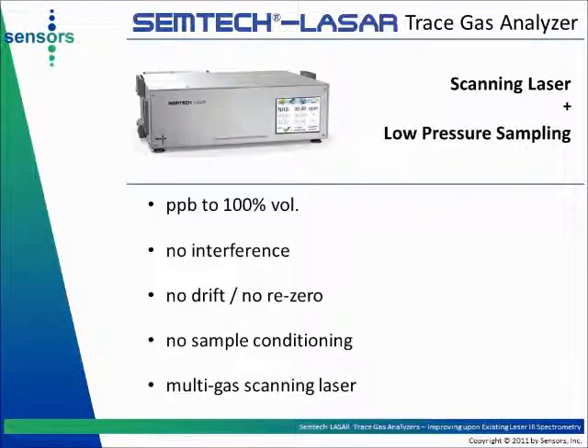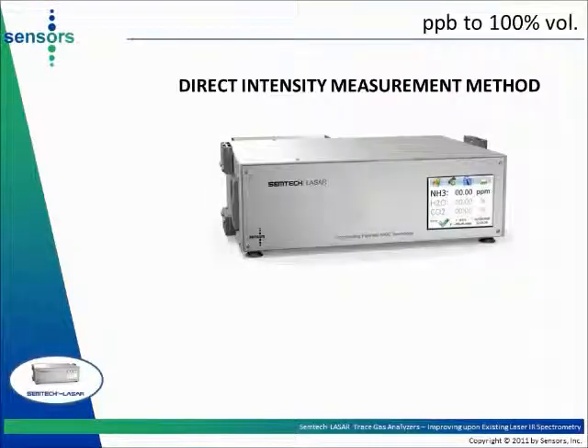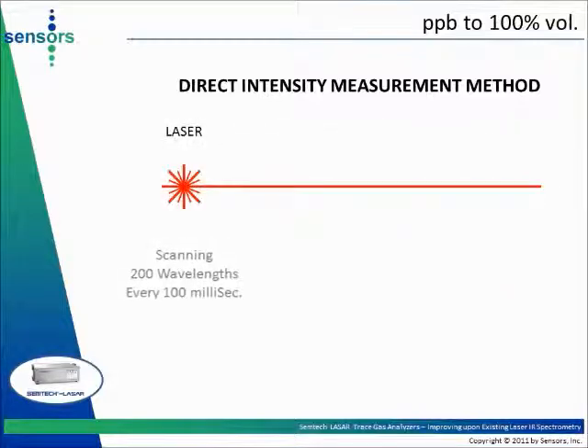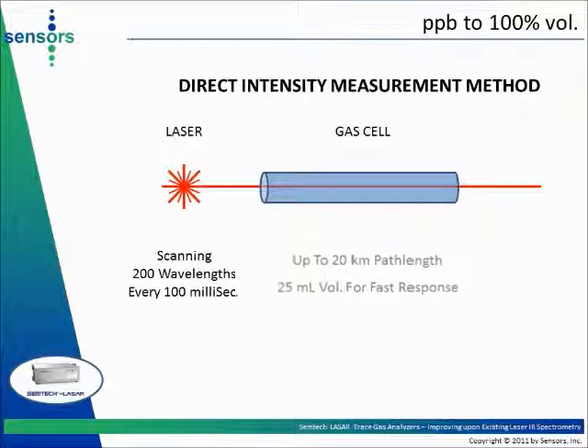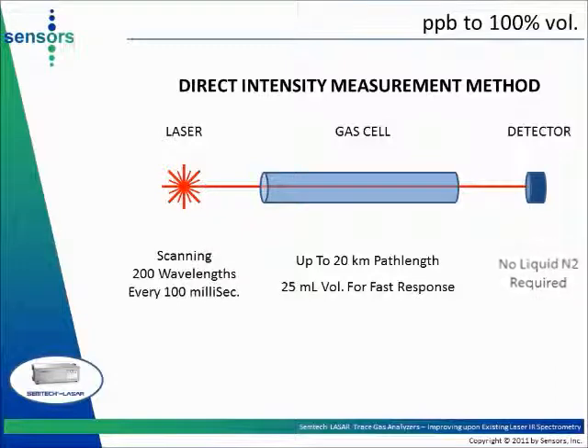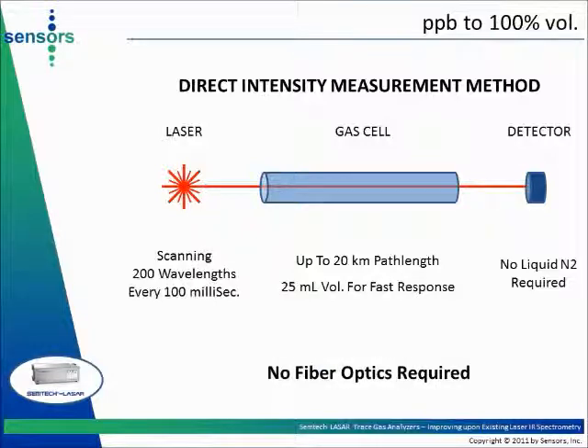Low-pressure sampling enables operation without sample conditioning for most applications. Scanning lasers enable measurement of several gases using a single laser. The Semtech LASAR is a direct-intensity measurement spectrometer — it does not rely on ring-down-time measurement to calculate gas concentrations. This simple spectrometer consists of a laser scanning 200 wavelengths every 100 milliseconds, a resonant cavity gas cell providing up to 20 kilometers of path length for increased sensitivity, and a detector that does not require liquid nitrogen cooling. The gas cell is only 25 milliliters in volume, allowing for fast response. No fiber optics are required, neither in the construction nor the operation of the analyzer.